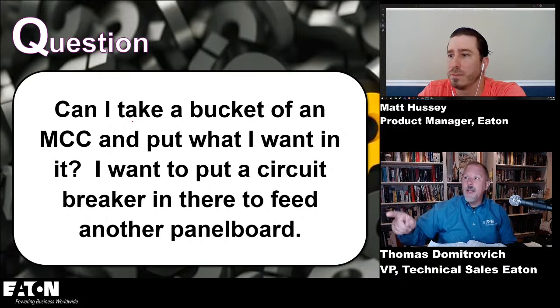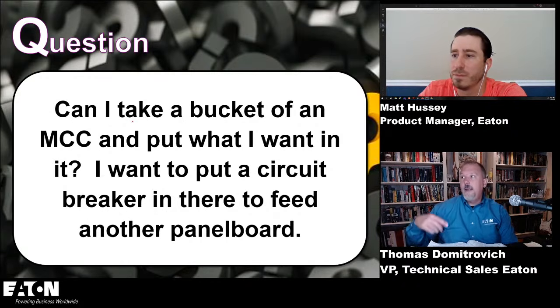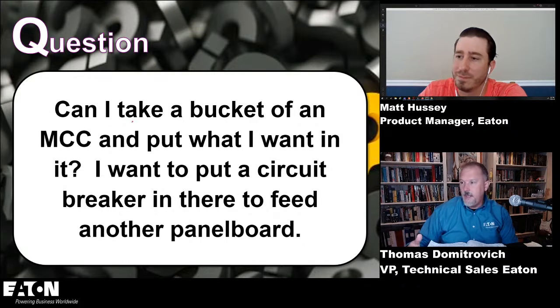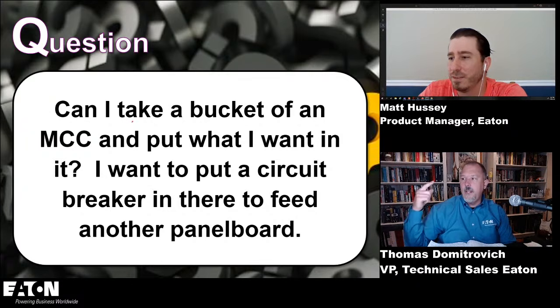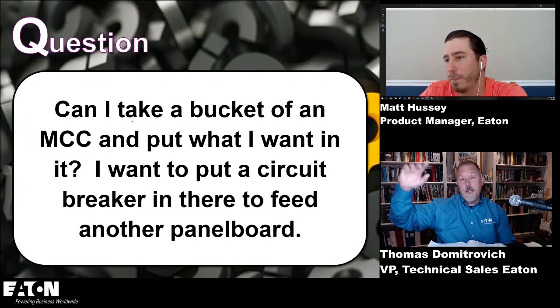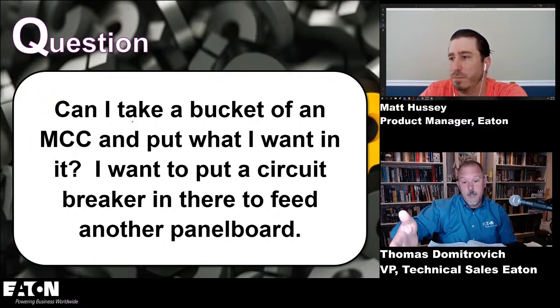Can I take a bucket of an MCC and put what I want in it? He wants to put a breaker in there to feed another panel board. So this guy sent the question in saying he has a panel board next to it. He has an empty bucket, or a spot in there. He wants to take the bucket out, put a breaker in there, and run a feeder over to that panel board. Matt, can he do that?